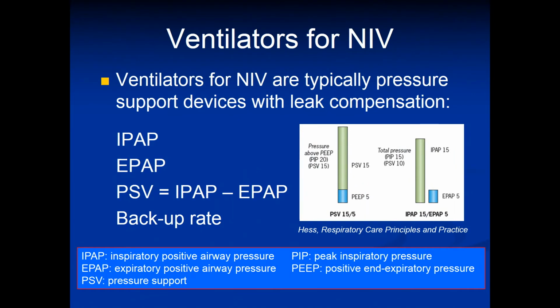Ventilators used for non-invasive ventilation can either be devices that were designed specifically for that purpose, or we can use a critical care type of ventilator. The devices that are designed for non-invasive ventilation are typically pressure support ventilators that have good leak compensation. On these devices, we will set an inspiratory positive airway pressure, or IPAP, and an expiratory positive airway pressure, or EPAP. The difference between the IPAP and the EPAP is the pressure support setting. The EPAP, for all practical purposes, is the same as positive end expiratory pressure, or PEEP.